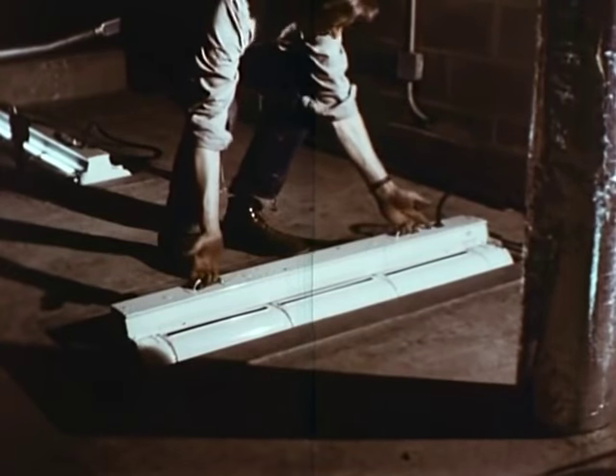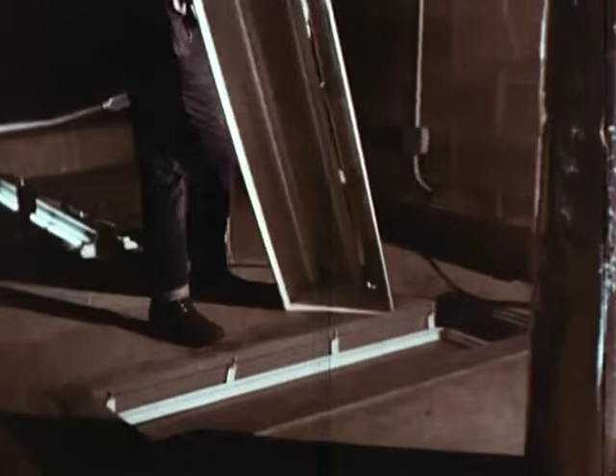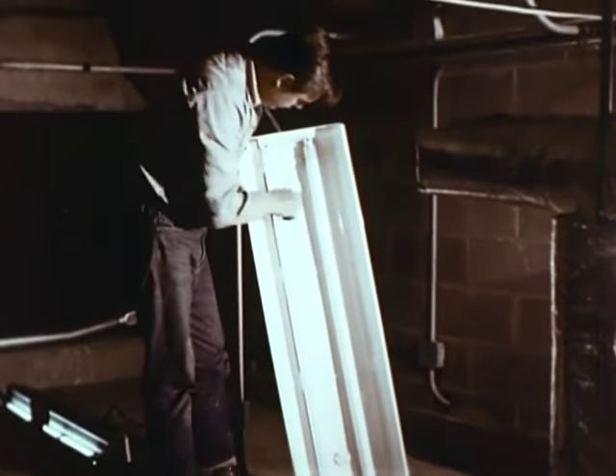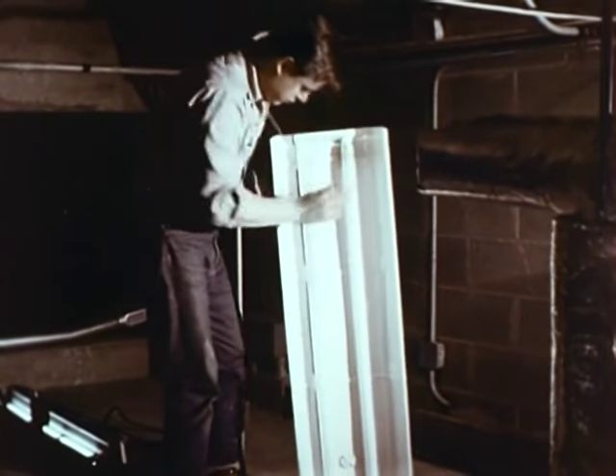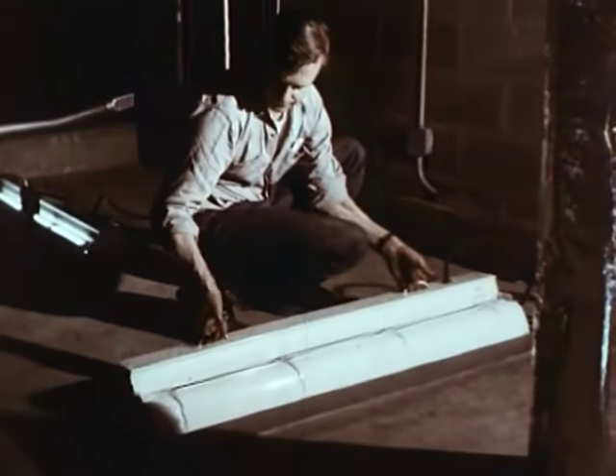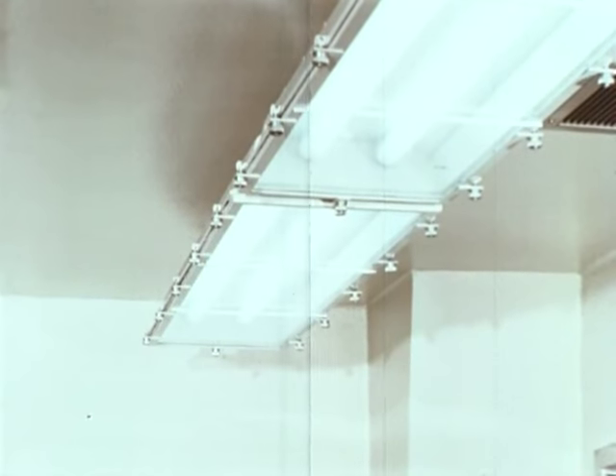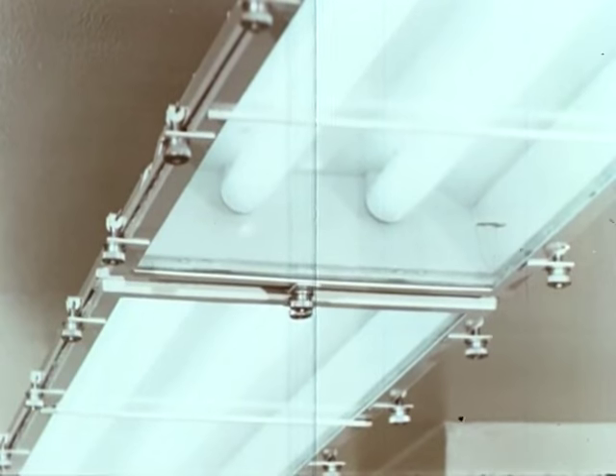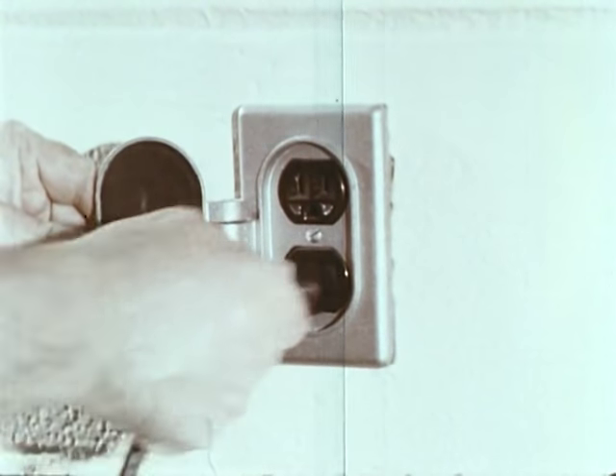Fluorescent fixtures may be ceiling mounted and serviced from within the room, or they may be installed above the ceiling encased in glass and serviced from a clean attic. A good gasketed seal is necessary to prevent the spread of contamination from the room into the attic. Where frequent washdowns of the area are necessary, watertight units such as these should be employed. Also, the electrical outlets in the room should be watertight to prevent water damage, and internally sealed to prevent leakage of contamination.